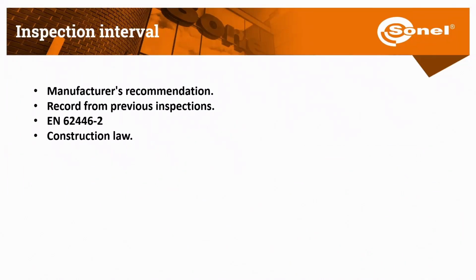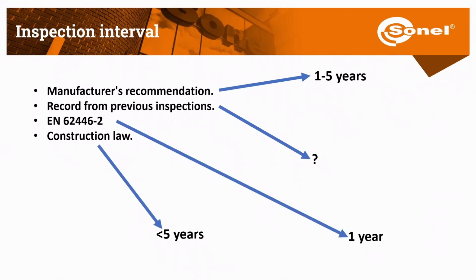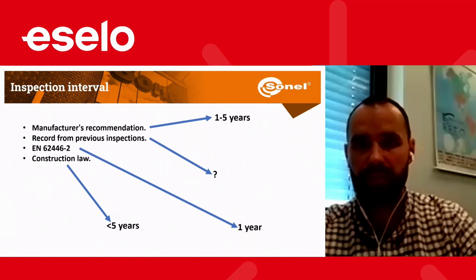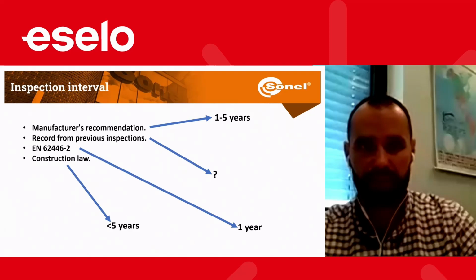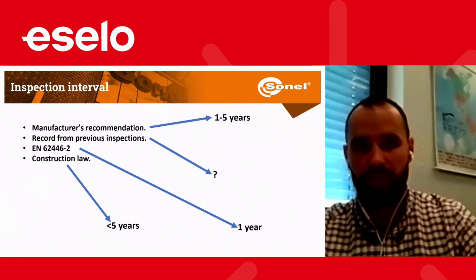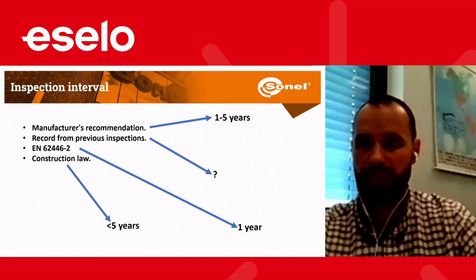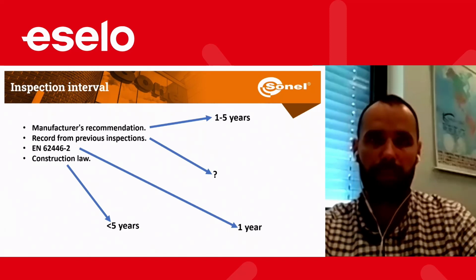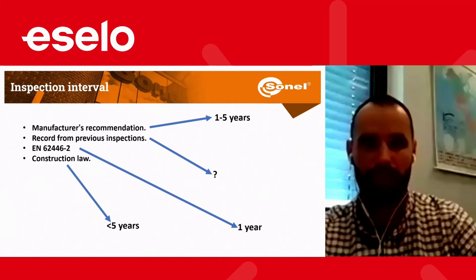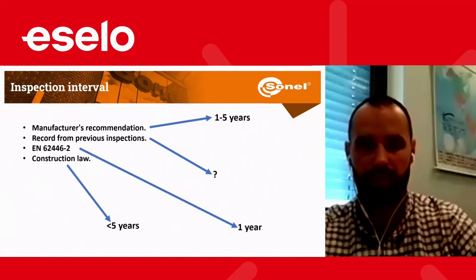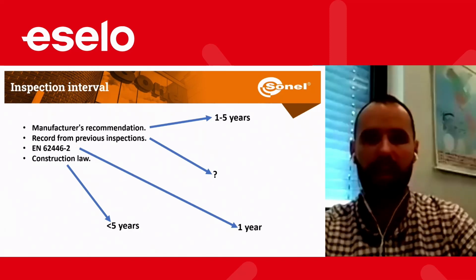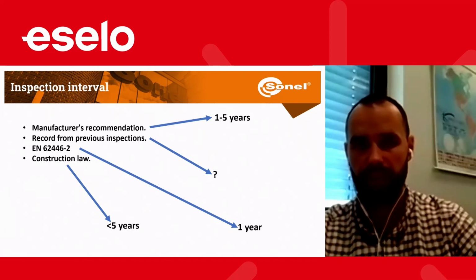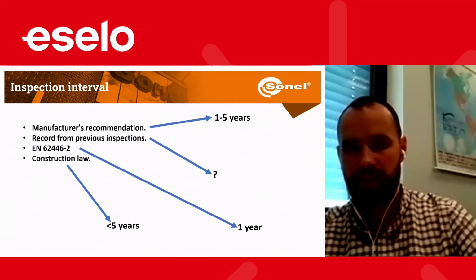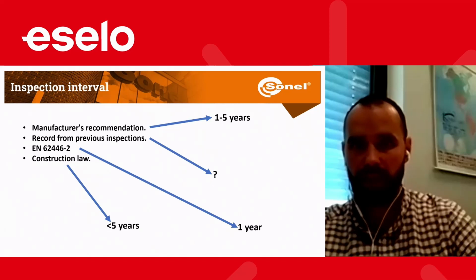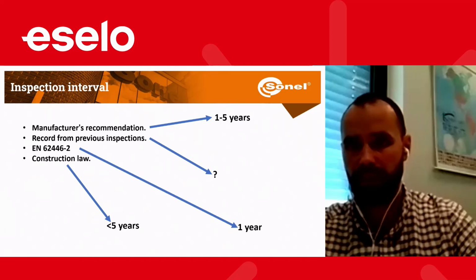Inspection intervals. When are we supposed to make the survey after the installation? Some of the manufacturers of the PV installations recommended, and this is safe, to make the surveys every 5 years. We can also rely on the reports from the previous inspection. So if we have the inspection every 2 years, and this is something that is stable over some period, so for example, the loop impedance test is same or roughly same as it was before, the test of the bonding and earth resistance is same, we can extend the period for a longer time. So instead of 2 years, we can keep it every 5 years measurement.